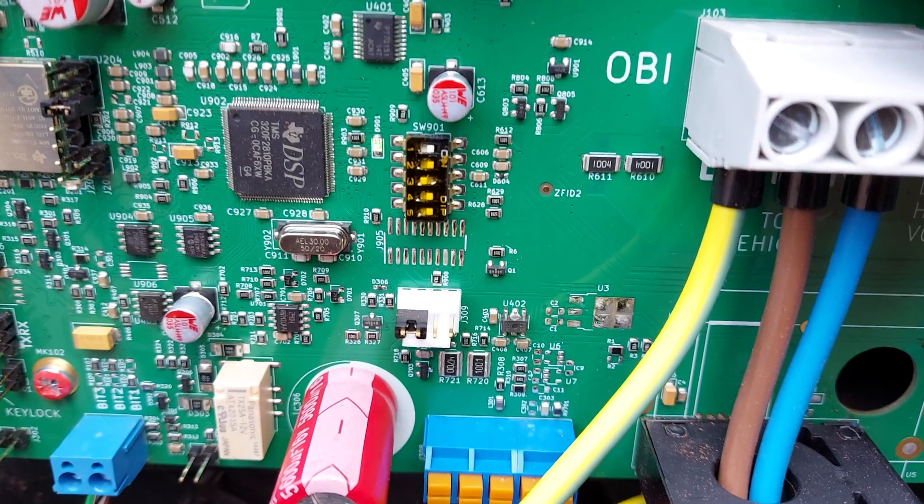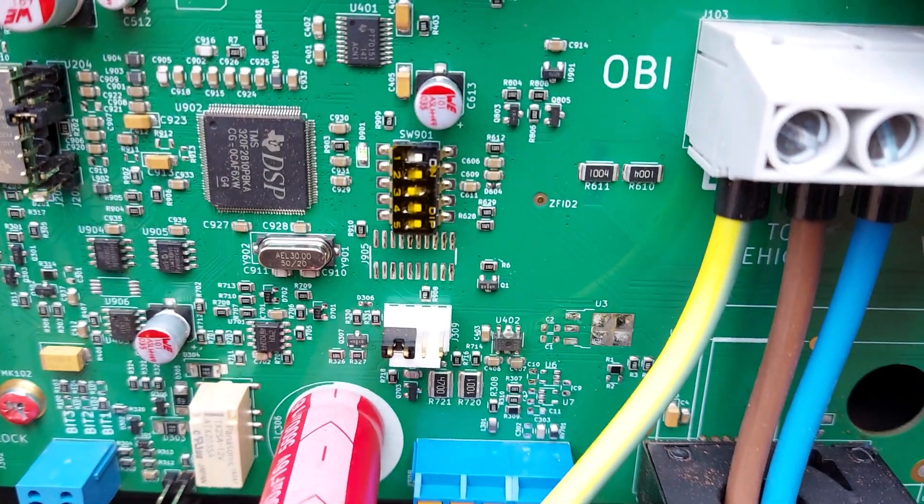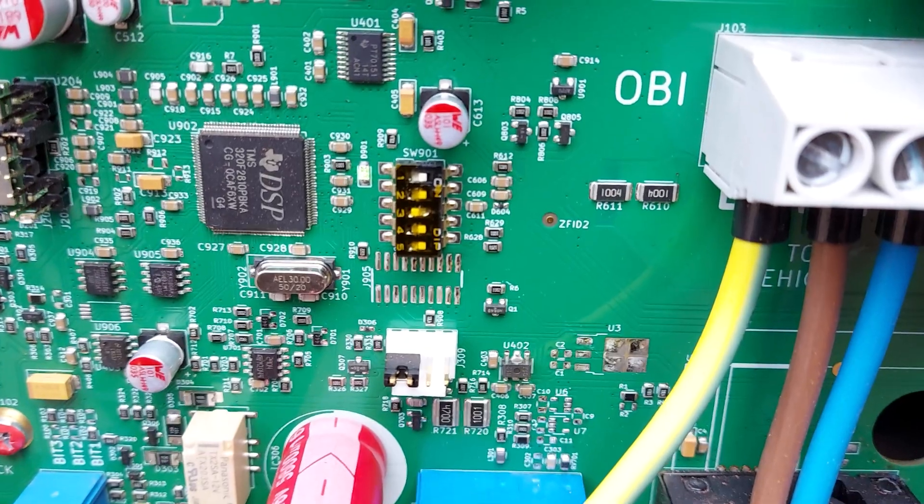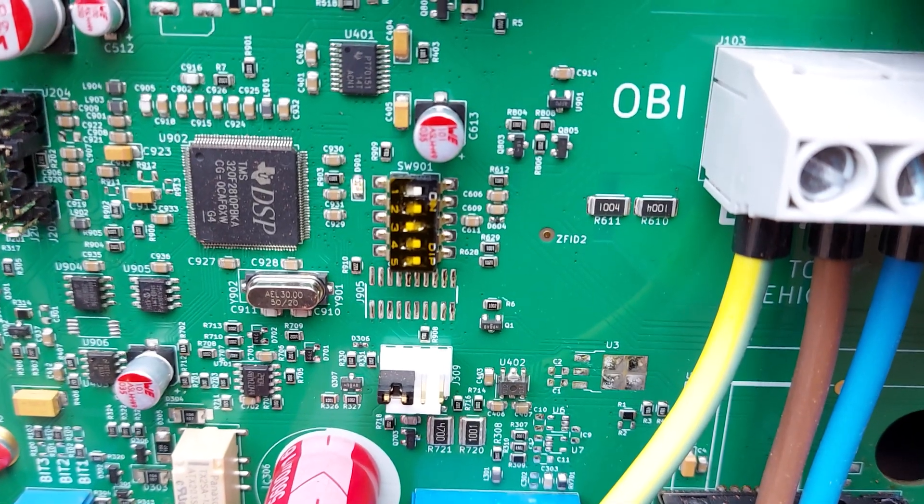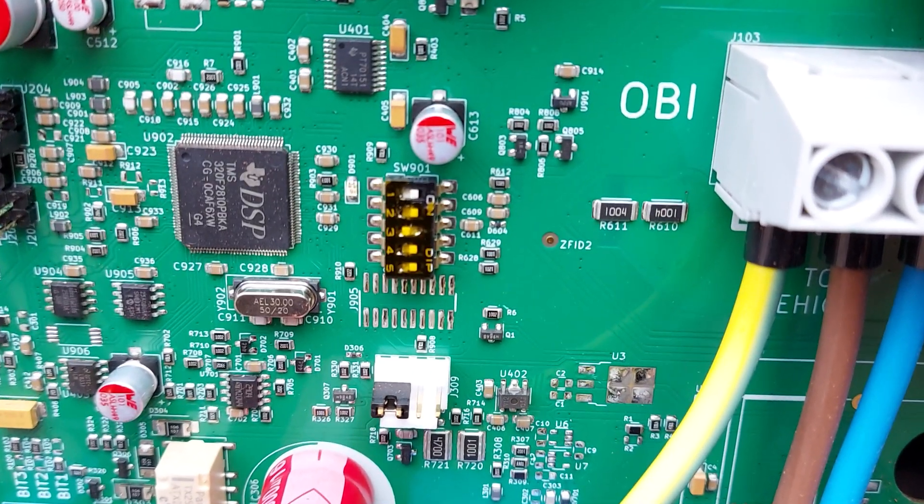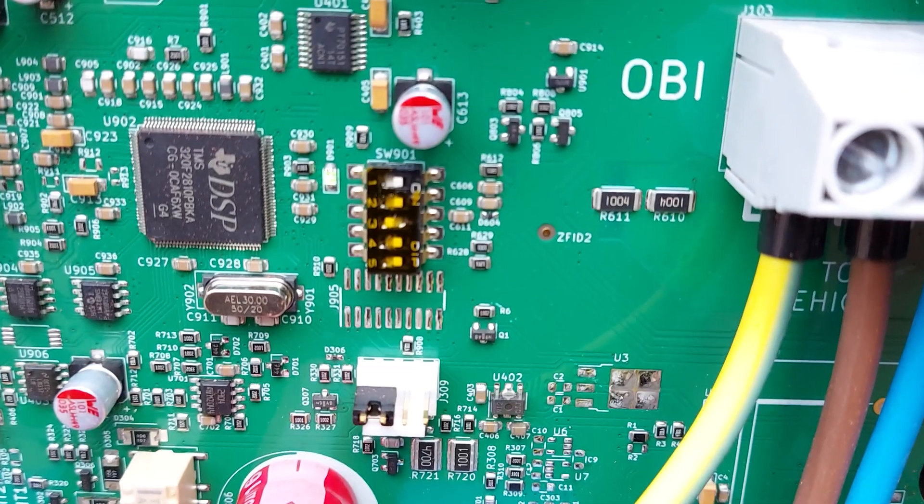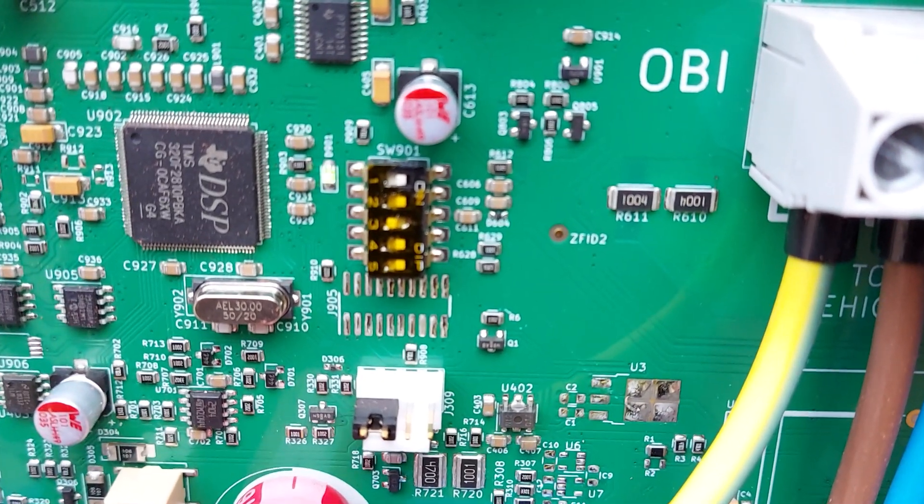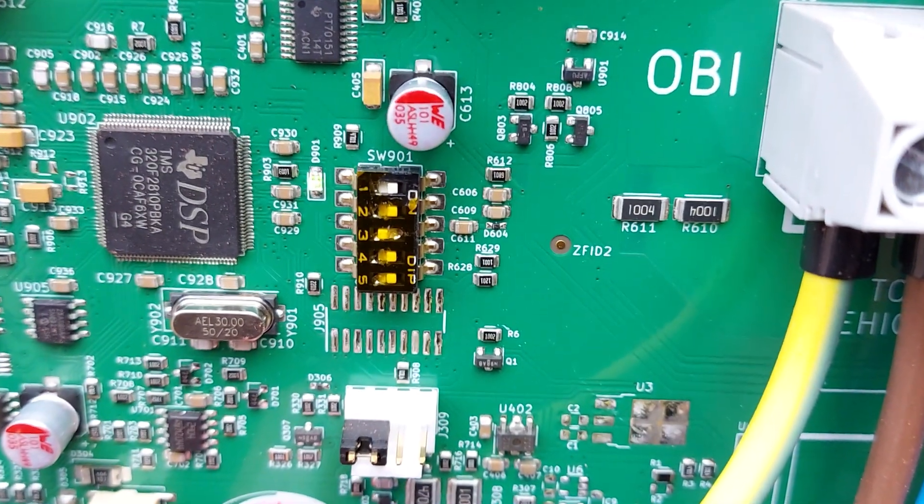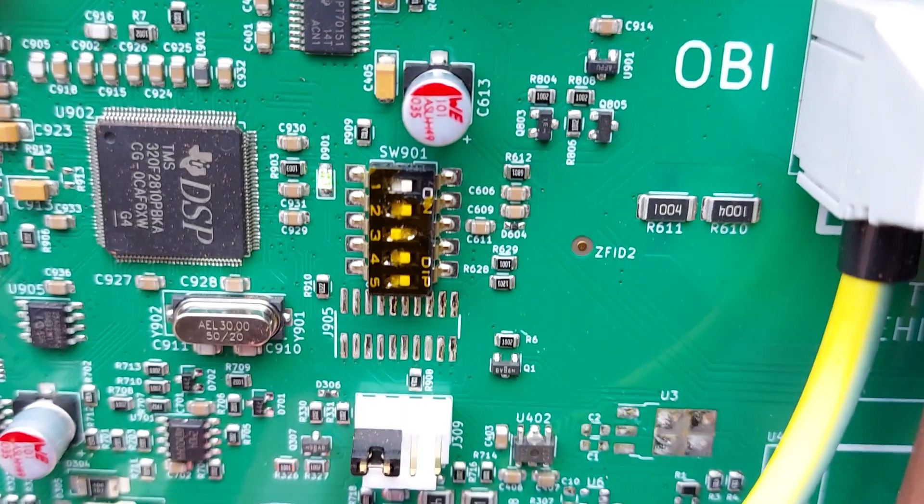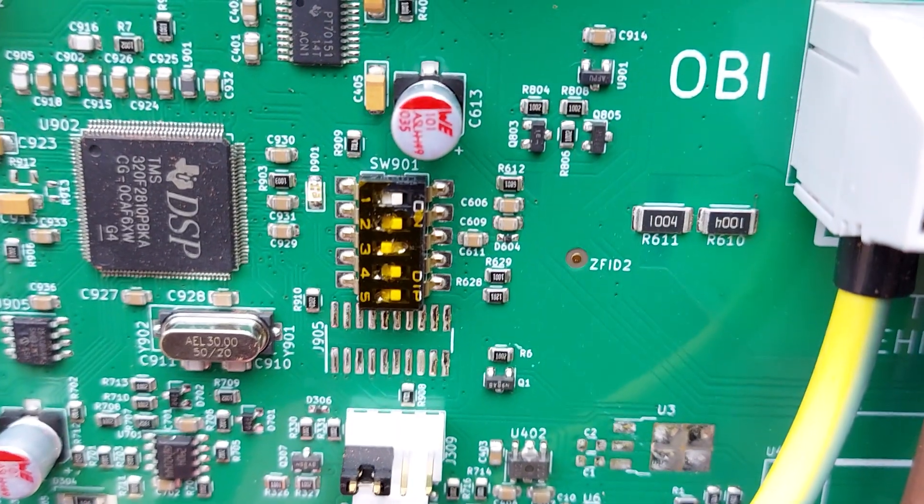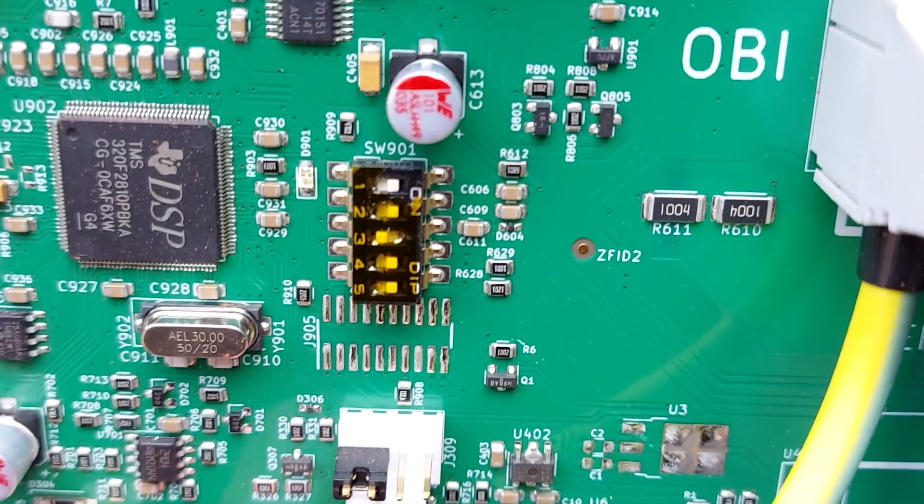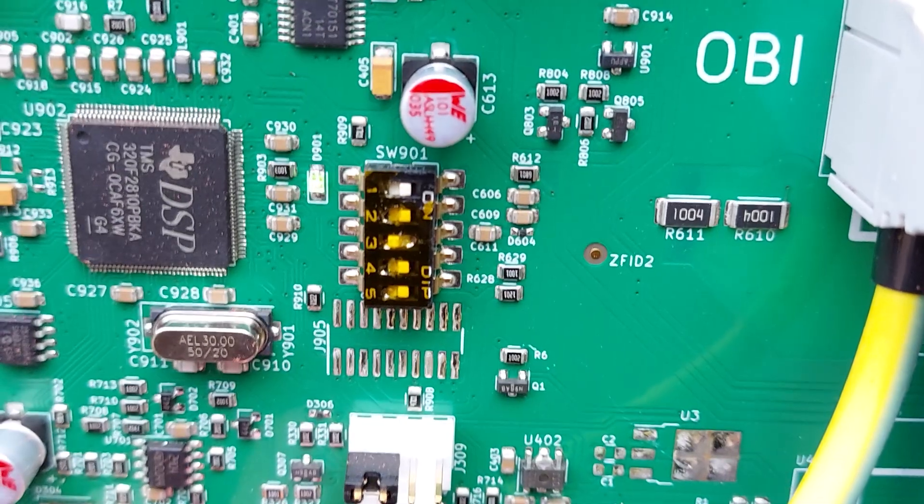Dip switches 1, 2, and 3 set the power rating of the unit, so under normal circumstances that's 7 kilowatts and that's 110. Switch number 4 is for the 60 amp fuse saver you can set on site. For other settings you need to refer to Podpoint. Switch number 5 is set to 1 if it's a tethered unit and set to 0 if it's a socketed or universal unit.